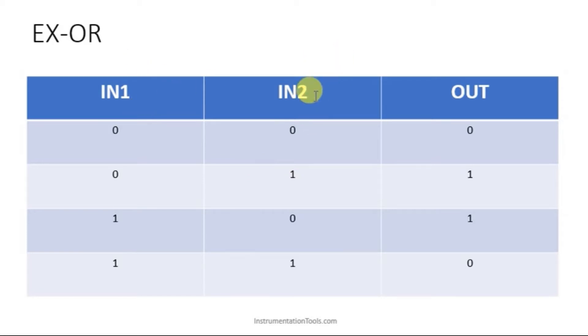With only two contacts we cannot make this logic. But we have only two inputs, so how do we get that extra contact? There is no need for an extra contact — you can use input one as both normally open and normally closed. Similarly for input two: in one place use it as normally open, in another place use it as normally closed. You can change the way of using the inputs, but it will be the same input with different conditions.